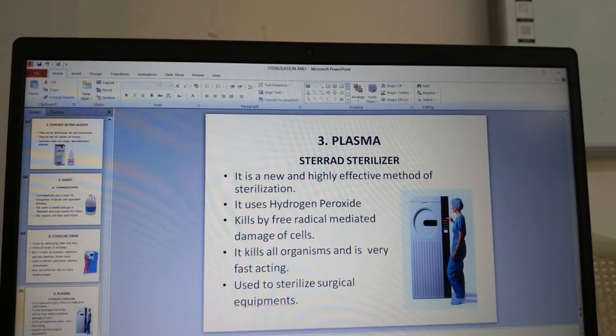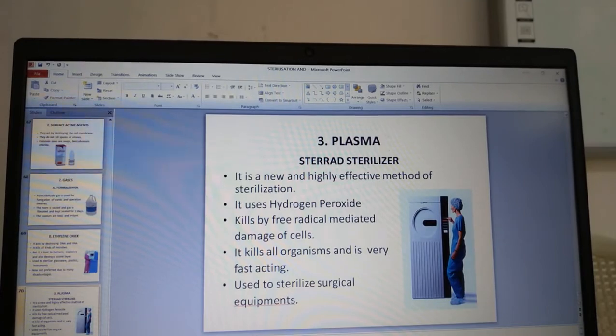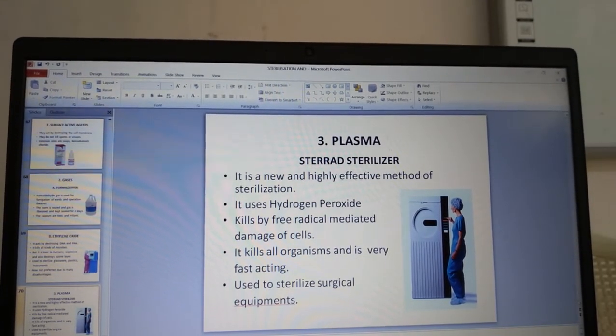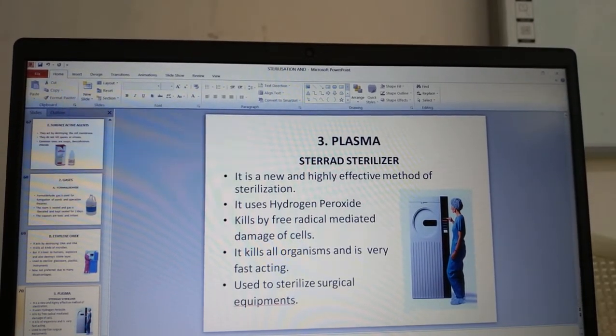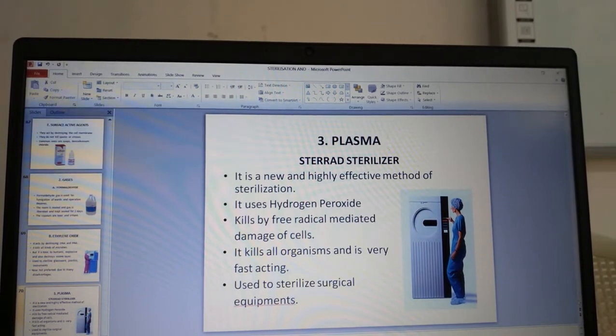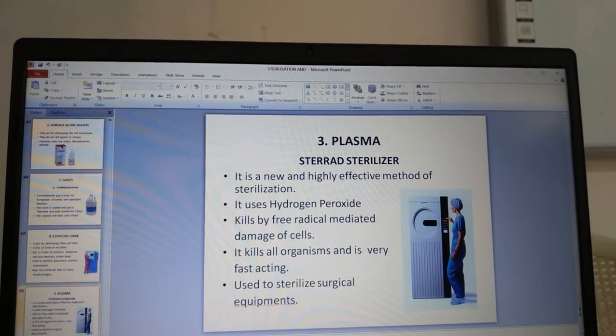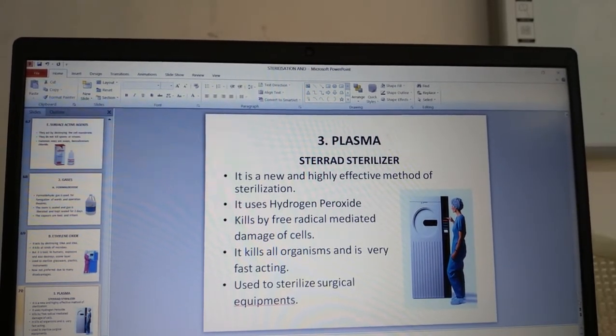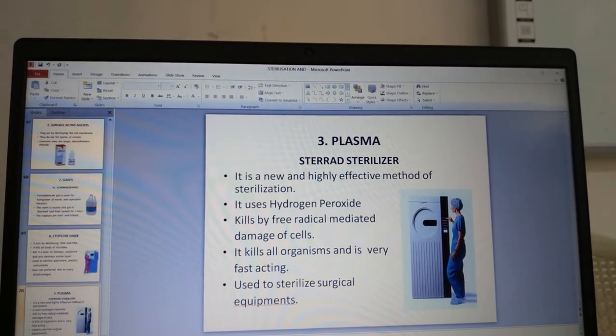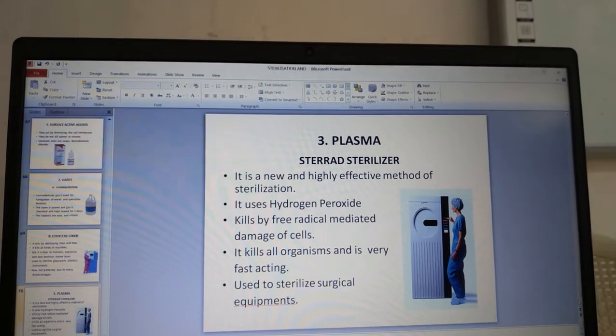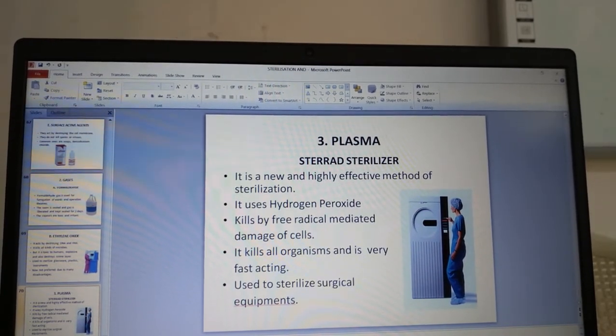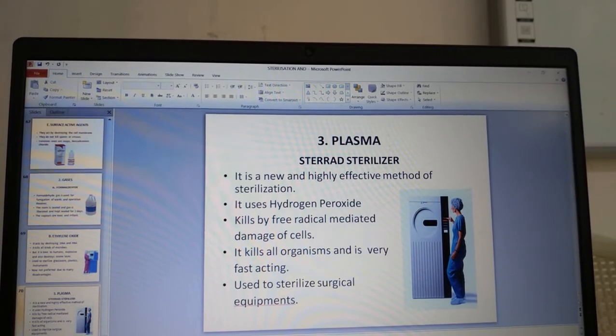Plasma sterilization uses the Sterrad sterilizer. It is a new and highly effective method using hydrogen peroxide plasma — an ionized gas consisting of positive ions and free electrons in proportions resulting in no overall electric charge. It kills by free radical-mediated damage to cells, kills all organisms, is very fast acting, and is used to sterilize surgical equipment.